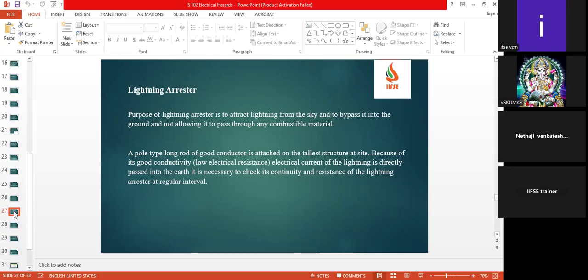It is about, if lightning happens nearby, it may contact our building. So the lightning arrestor will safeguard us by taking that high intensity of energy in a safer manner. It will discharge. If the lightning arrestor is not there, such high-voltage energy, if it strikes the building, has a chance of igniting any combustible materials, if there are any petroleum products or flammable chemicals. It will have a high chance to ignite those materials, resulting in a fire accident.